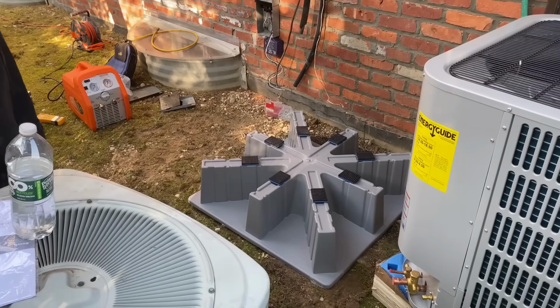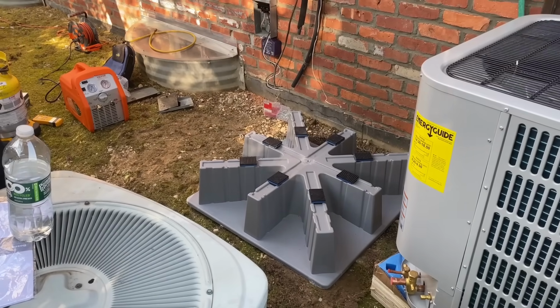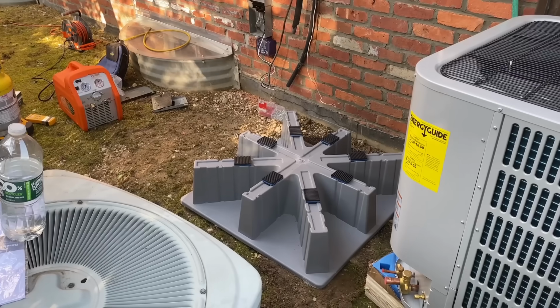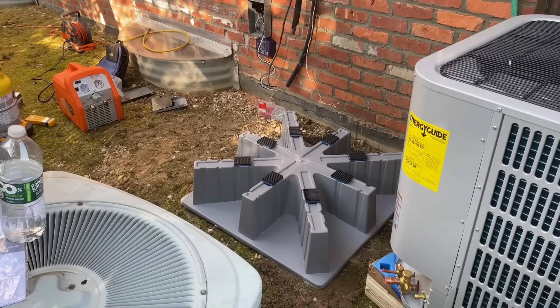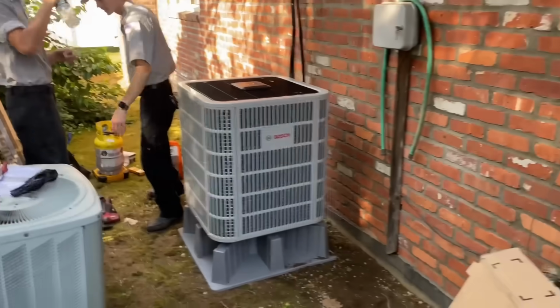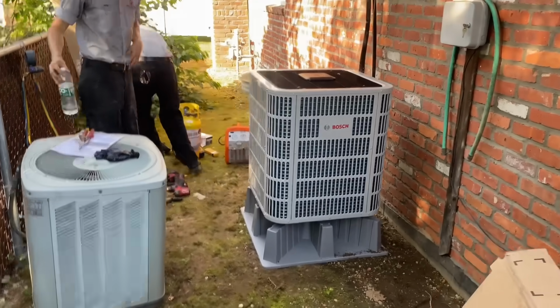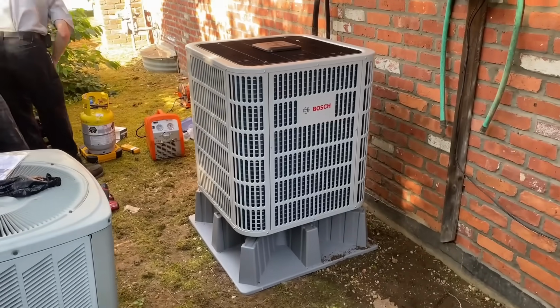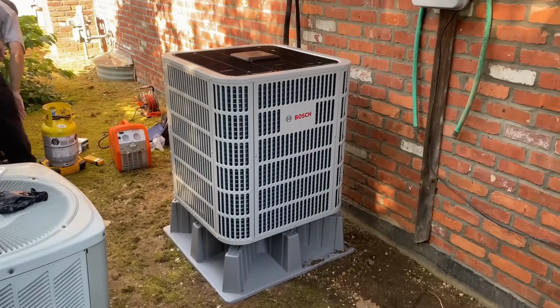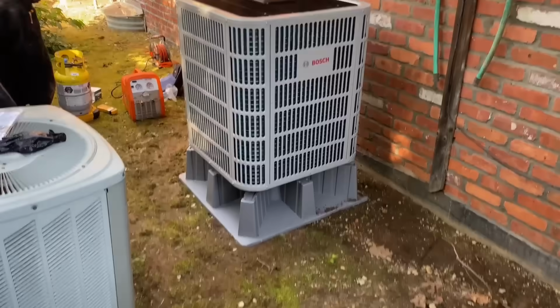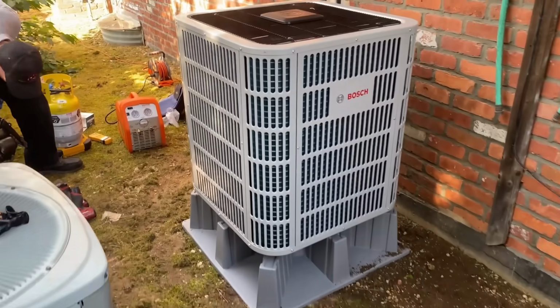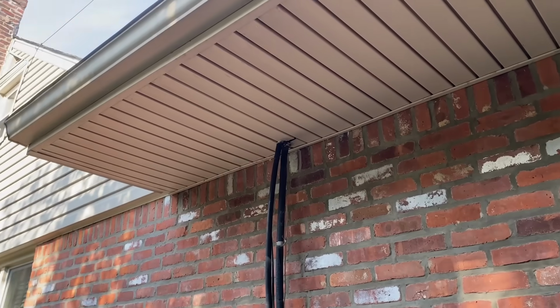We incorporate the Diversitech riser pad in all of our heat pump condenser installations. We have the condenser level, well, pretty damn close to level as it's going to get. Pad is set. Now I have to run new line set, new drain.